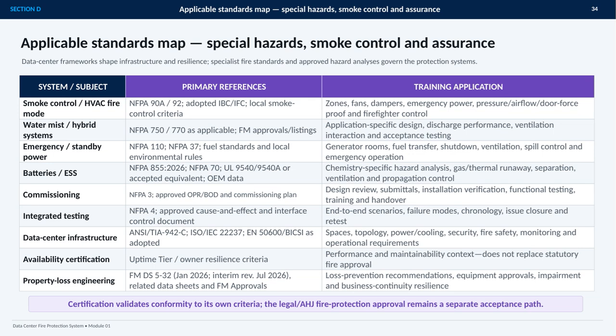Water mist or hybrid systems require application-specific design, approved equipment, and acceptance testing. Emergency power, batteries, and energy storage systems bring in NFPA 110, NFPA 855, NFPA 70, UL standards, and manufacturer data. Commissioning and integrated testing then verify that systems work individually and together, including cause and effect sequences, failure modes, retesting, and handover. The broader infrastructure frameworks, such as ANSI/TIA-942-C and ISO/IEC 22237, address resilience, topology, power, cooling, security, and operations. Uptime criteria and FM guidance add performance and loss prevention context. Certification does not replace legal fire protection approval by the authority having jurisdiction. Each framework validates its own criteria, while statutory acceptance remains a separate path.